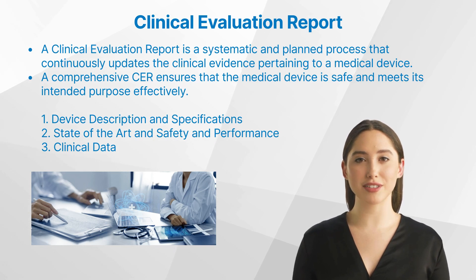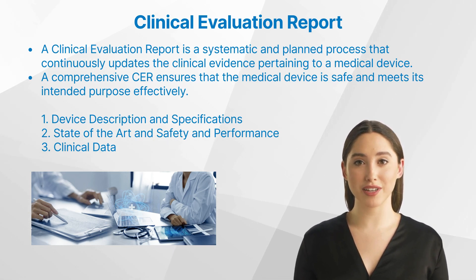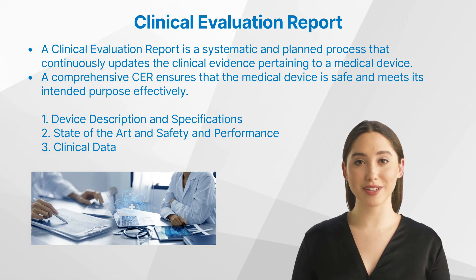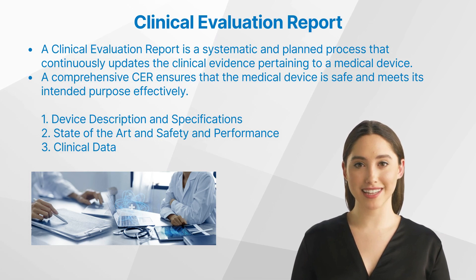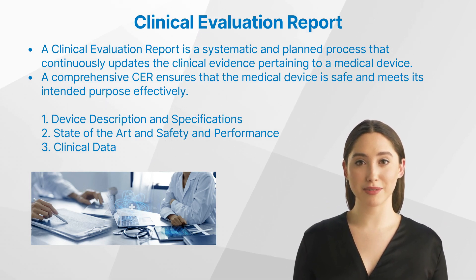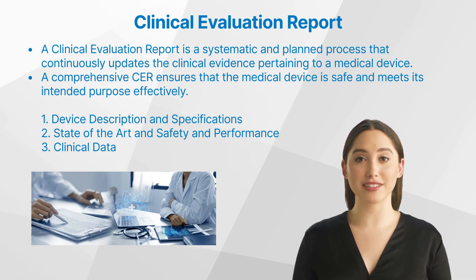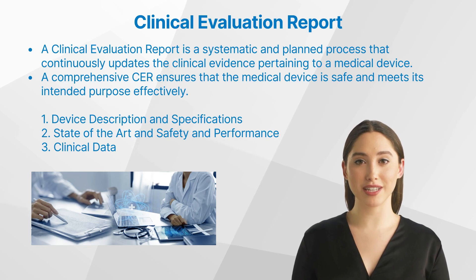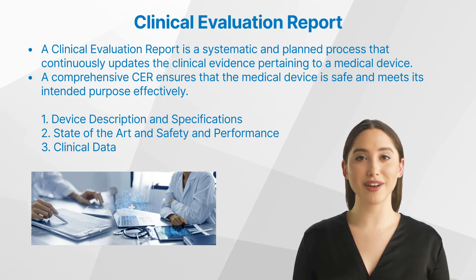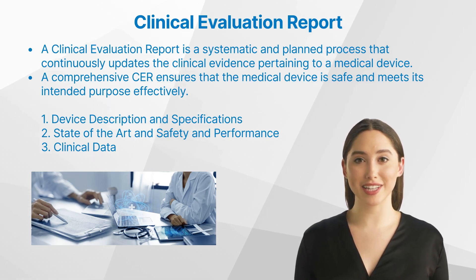One: device description and specifications. The first component involves providing a detailed description of the device, including its purpose and function. This includes details about its design, components, principles of operation, and proposed medical indications. A comprehensive device description helps regulators understand how the device works and its intended use.